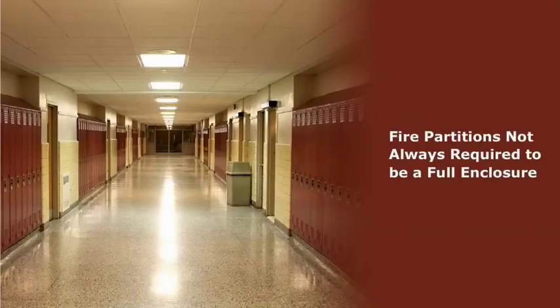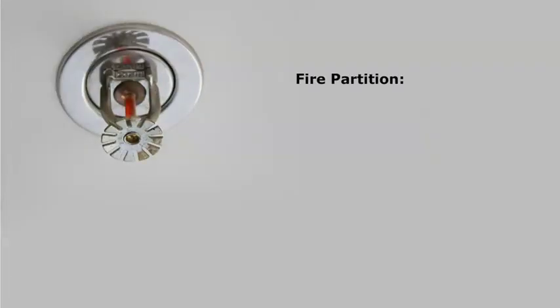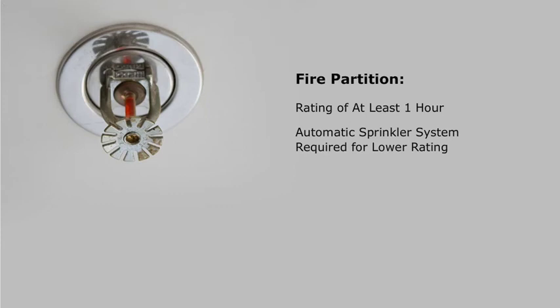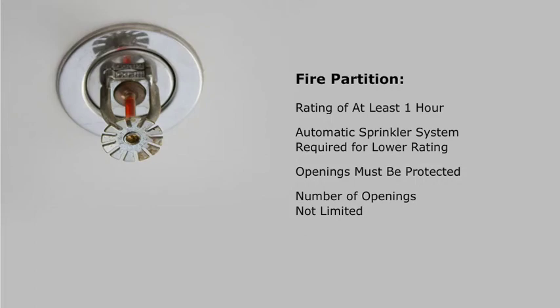A fire partition separates one area from another but is not always required to be a full enclosure. The floor and ceiling assemblies typically need to have the same rating, but when used to separate tenant spaces in malls, dwelling units, sleeping areas, corridors, or certain construction types, they do not. A fire partition usually has a rating of at least one hour, though corridor walls and walls between dwelling and sleeping units are allowed to have a lower rating, often requiring an automatic sprinkler system. Like fire barriers, openings in fire partitions are required to be protected, although the number of openings is not limited.